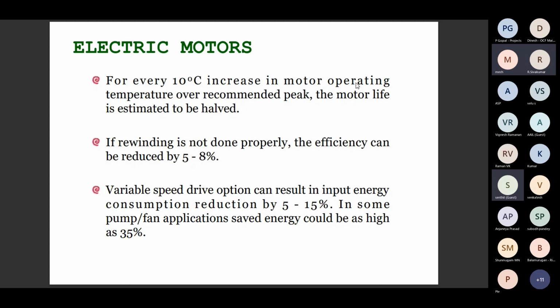And wherever it is possible, a variable speed drive option can be used to reduce energy consumption by 5 to 15%. In some cases, especially fans and blowers, you can achieve 25% also. This is also based on the application. So the variable speed drive saves a minimum of 5 to 15% of the energy, and in some pump and fan applications, you can save up to 35%. So wherever it is possible, the VFD can be adopted. Sometimes it is called a variable speed drive, VSD. Basically, in commercial terms, it is called a variable frequency drive. Next one.